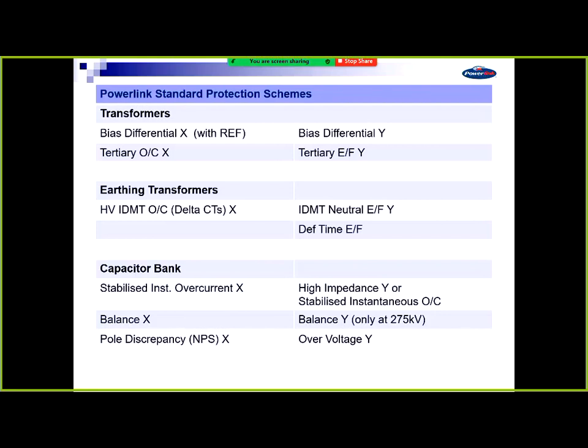They're totally separate networks, totally separate CTs, VTs, totally separate circuitry, batteries, relays, everything is separate. The trip coils on the breakers are separate. The only thing common is the circuit breaker because of the cost. So we cover that by having duplicate breakers, and a circuit breaker fail scheme that covers that.